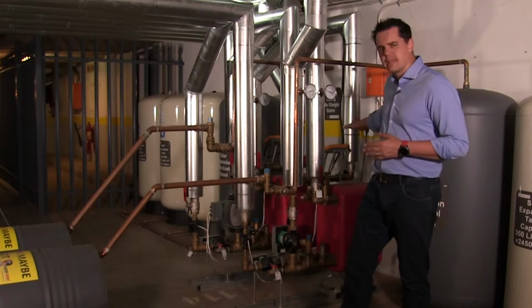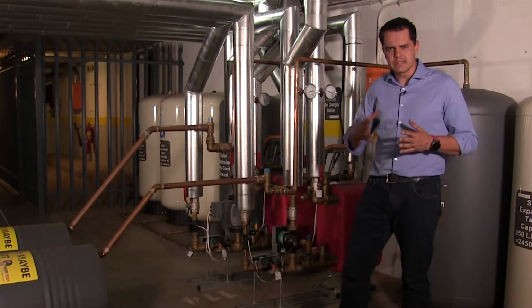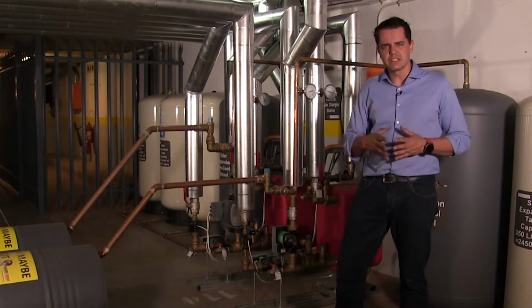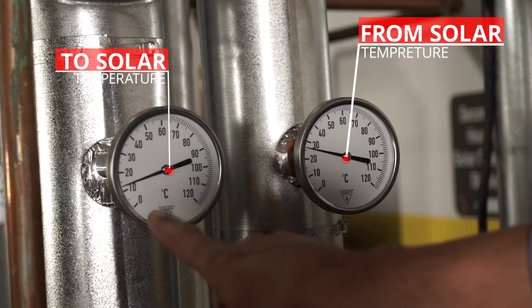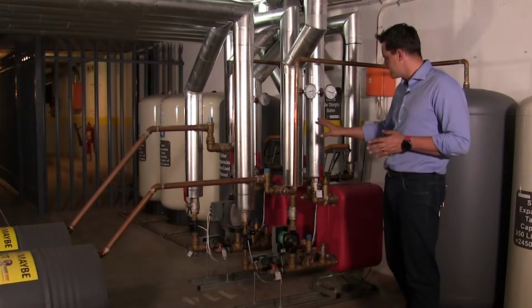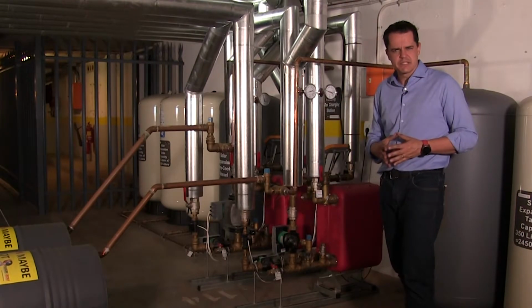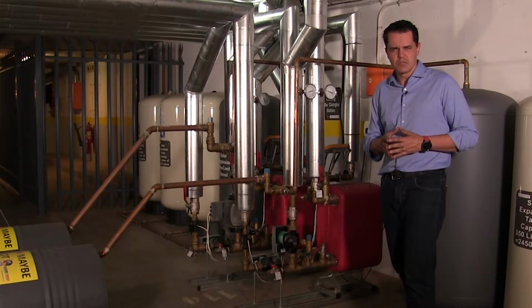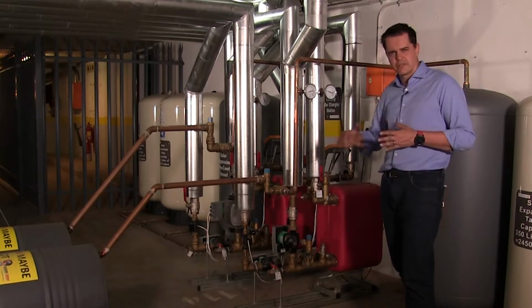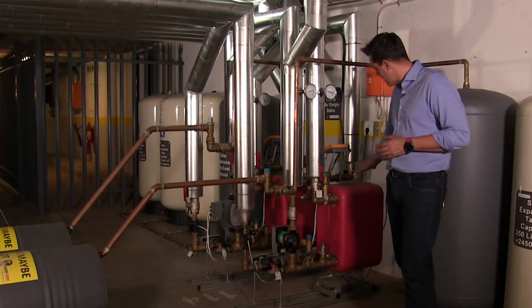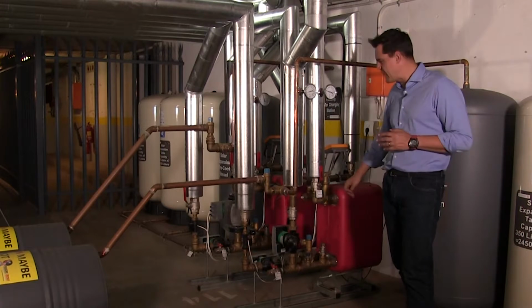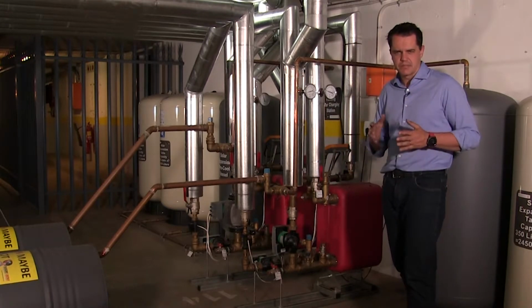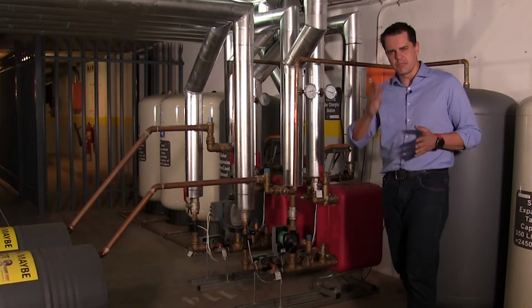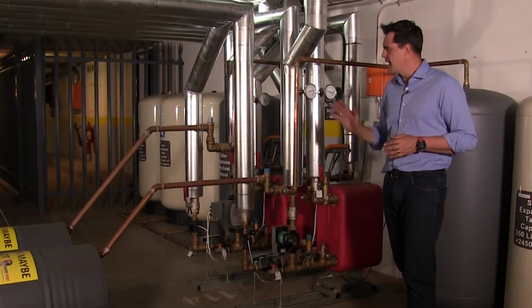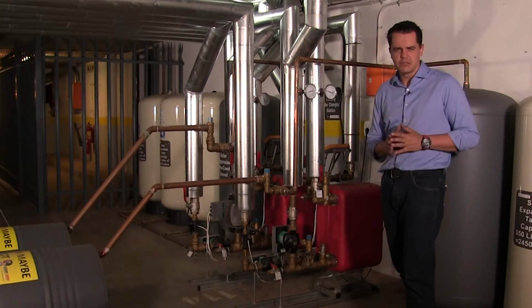If you can in fact see that there's a display, the next item to check is: is there circulation? Here are our two pipes coming in and out of the solar plant. So this again is exactly the same setup as we have at David Webster and Bernardo Hall. It's just a different size setup. We have our plate heat exchanger at the back, and it's an indirect system. So the liquid that goes up to the solar plant and the liquid in the tanks don't mix.